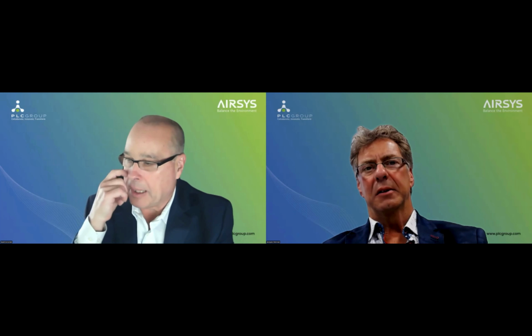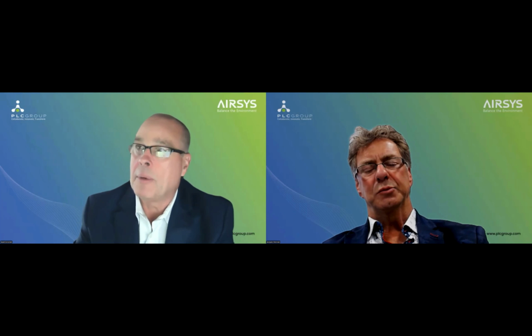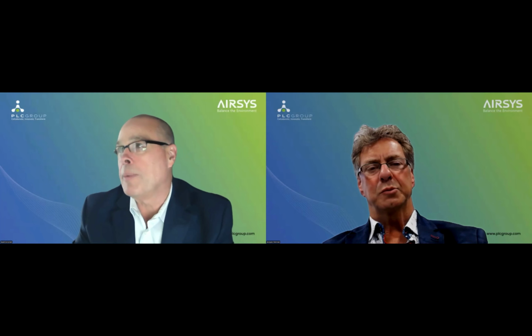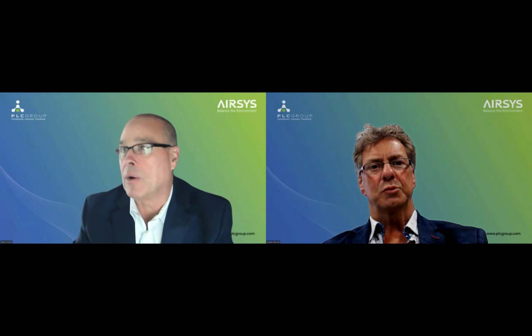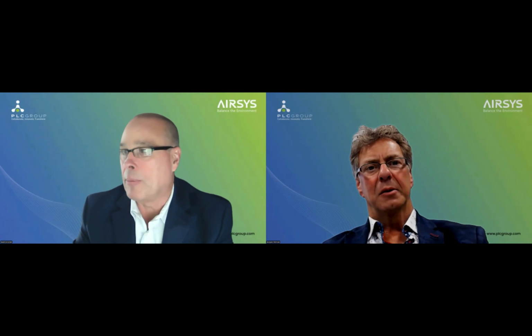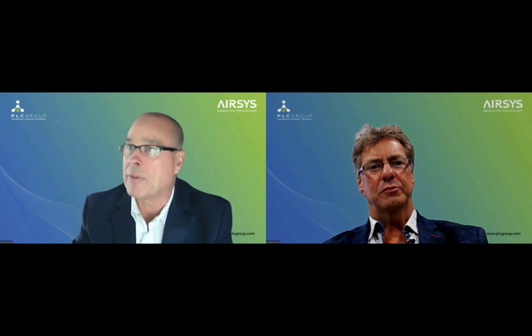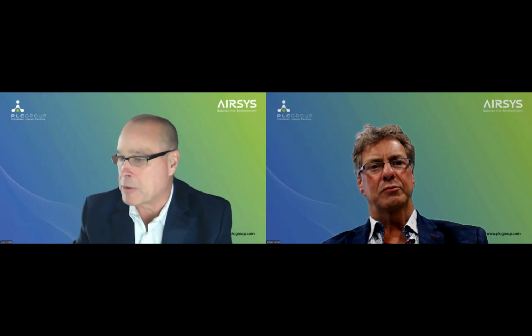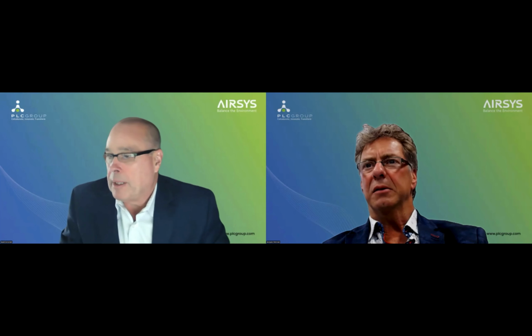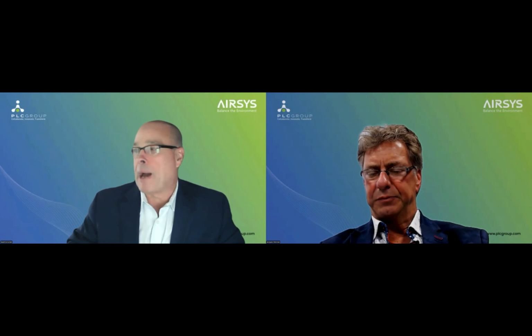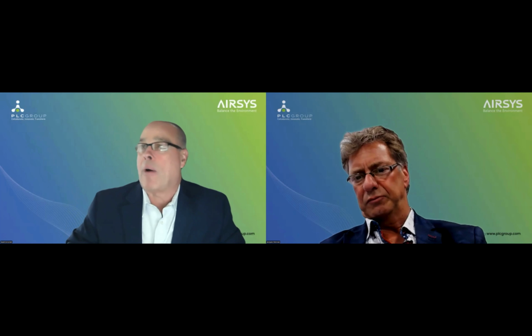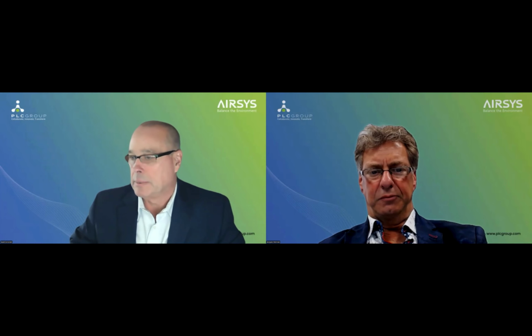So the common deployment issues are sometimes there are too many turns, especially with DX units going to the condenser for heat rejection. Too many elbows. The length run is over 200 feet in length. So it's certain things like that. If I'm answering your question, Harun, correctly. But those challenges are more site challenges and more installation challenges than anything else. When the unit arrives, are the pipes there and is it ready to go? Is the power set and the unit powered up when it's supposed to be? So those are just some of the common challenges that we face on a regular basis, just like any other manufacturer would.